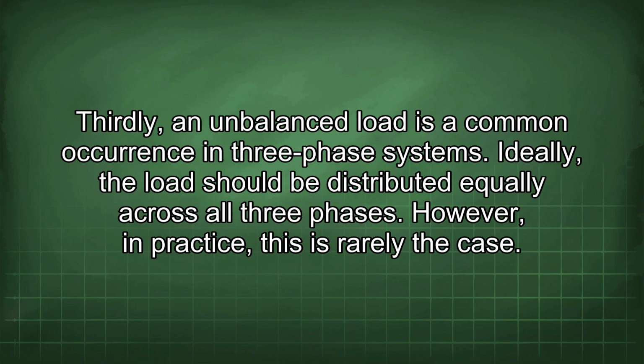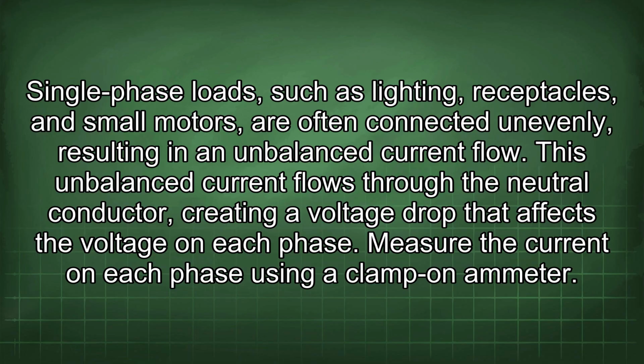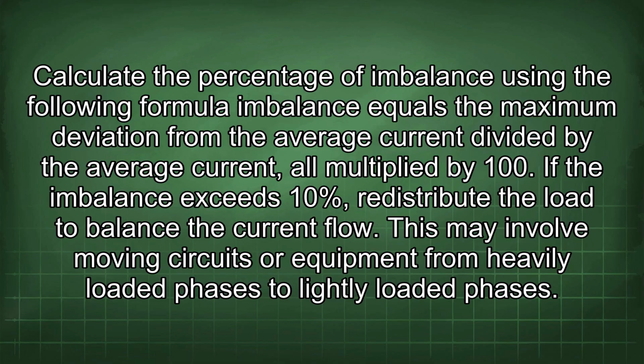Ideally, the load should be distributed equally across all three phases. However, in practice, this is rarely the case. Single-phase loads such as lighting, receptacles, and small motors are often connected unevenly, resulting in an unbalanced current flow. This unbalanced current flows through the neutral conductor, creating a voltage drop that affects the voltage on each phase. Measure the current on each phase using a clamp-on ammeter. Calculate the percentage of imbalance using the following formula. Imbalance equals the maximum deviation from the average current divided by the average current, all multiplied by 100.